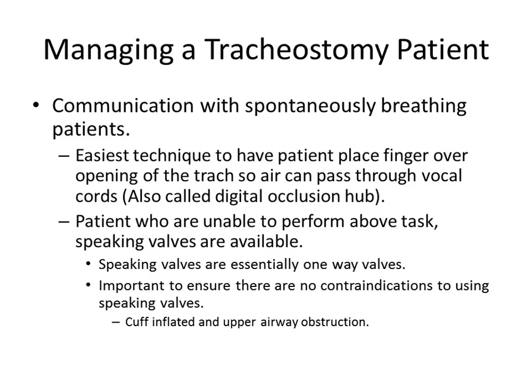As I said, there are passive Passy-Muir valves available, and if oxygen is needed, some of the valves do have the ability to place oxygen in line. Also, we can place a patient with a tracheostomy on a trach collar to provide some oxygen on top of the passive Passy-Muir valve. The passive Passy-Muir valve also can be used in line with the ventilator. These can be used so that patients are able to talk while they're on a ventilator. Just remember that the voice is going to be lower, since the amount of air that's expelled through the vocal cords is not as much as when the patient's off the ventilator.